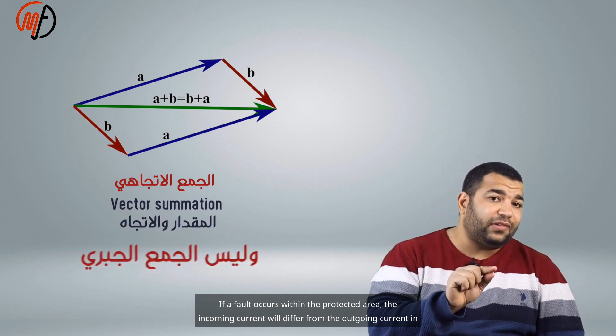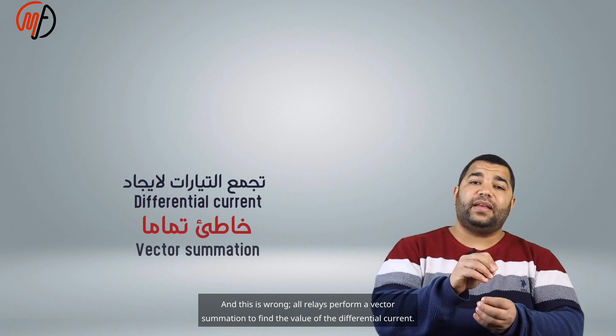If a fault occurs within the protected area, the incoming current will differ from the outgoing current in magnitude and direction, creating the differential current. Sum of currents means vector summation, focusing on magnitude and direction, not algebraic summation. All relays perform a vector summation to find the value of the differential current. In the event of a fault within the area to be protected, the incoming current will differ from the outgoing current, which creates a difference that leads to what we call the differential current.